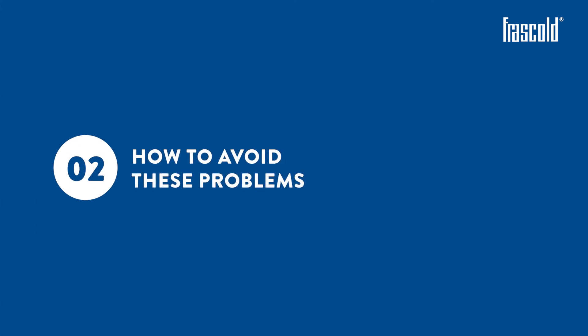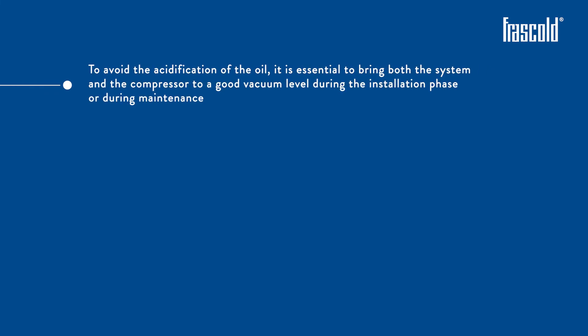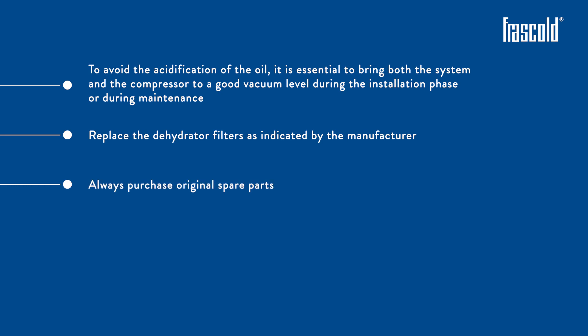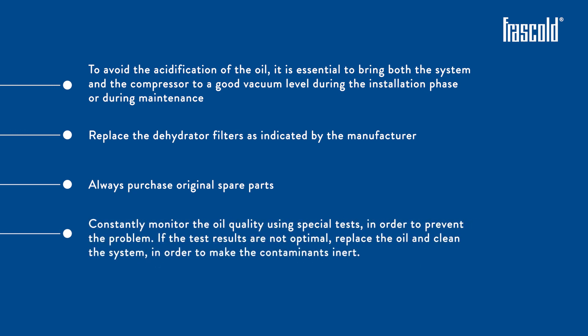How to avoid these problems? To avoid the acidification of the oil, it is essential to bring both the system and the compressor to a good vacuum level during the installation phase or during maintenance. Replace the dehydrator filters as indicated by the manufacturer, and always purchase original spare parts. Finally, constantly monitor the oil quality using special tests in order to prevent the problem. If the test results are not optimal, replace the oil and clean the system in order to make the contaminants inert.